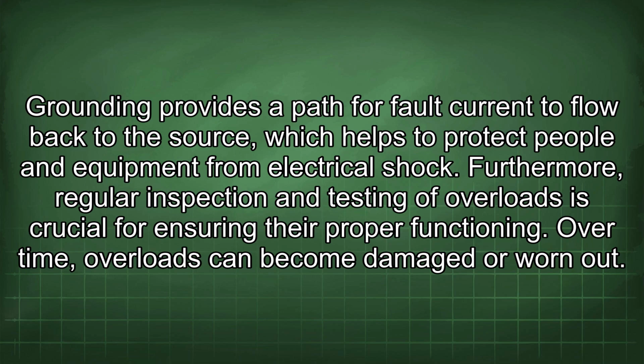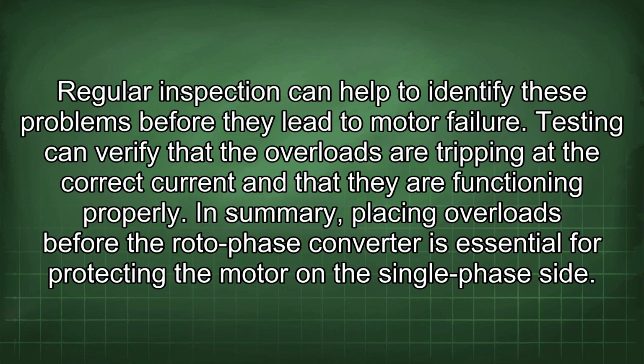from electrical shock. Furthermore, regular inspection and testing of overloads is crucial for ensuring their proper functioning. Over time, overloads can become damaged or worn out. Regular inspection can help to identify these problems before they lead to motor failure. Testing can verify that the overloads are tripping at the correct current and that they are functioning properly.